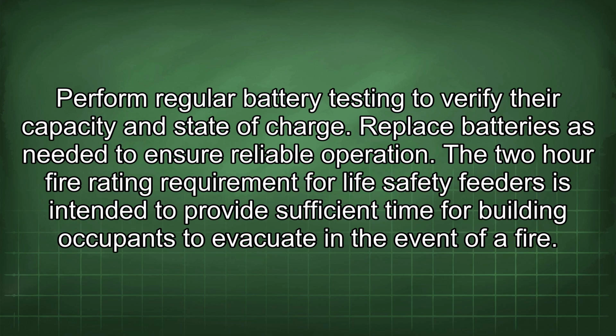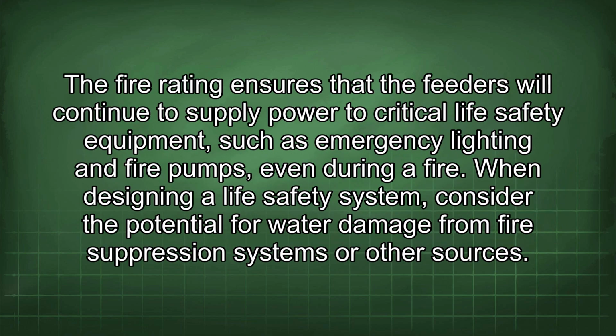The 2-hour fire rating requirement for life safety feeders is intended to provide sufficient time for building occupants to evacuate in the event of a fire. The fire rating ensures that the feeders will continue to supply power to critical life safety equipment, such as emergency lighting and fire pumps, even during a fire.